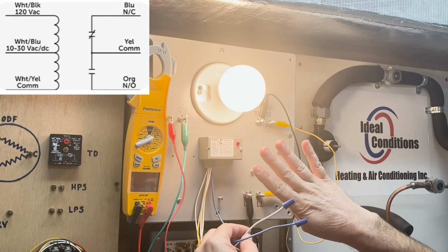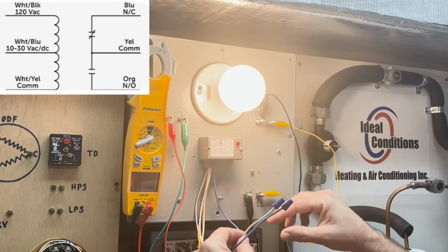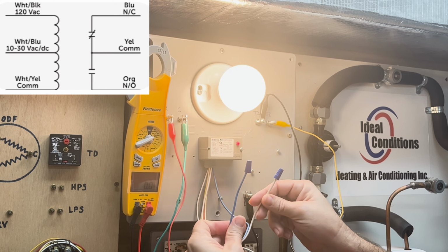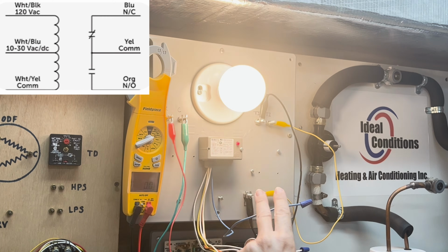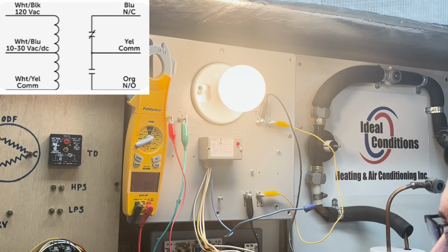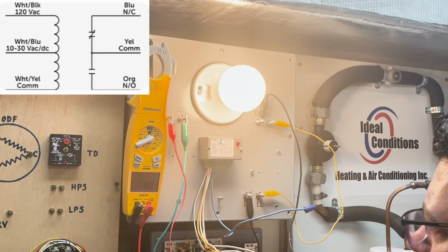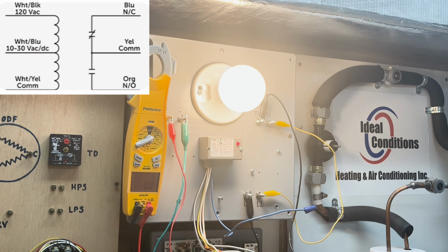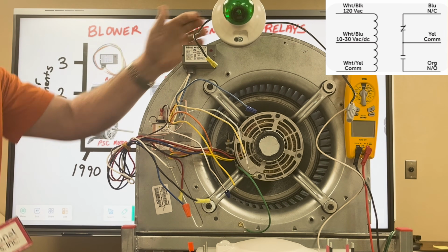I'm only going to use 4 of those wires in any of these applications here, so the other two have to be capped off. I'm going to go ahead and wrap up at the CANTEX box, take it over to the fan motor, and show you how to use more of these wires over there where I have a neutral present. Stay tuned. Okay, now we're over at the fan motor.